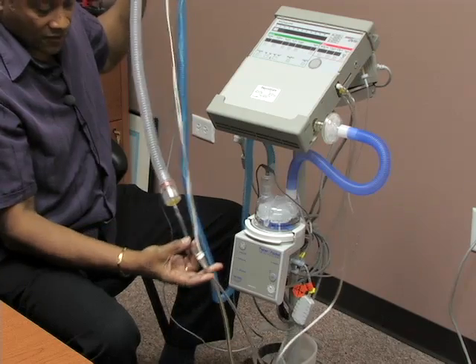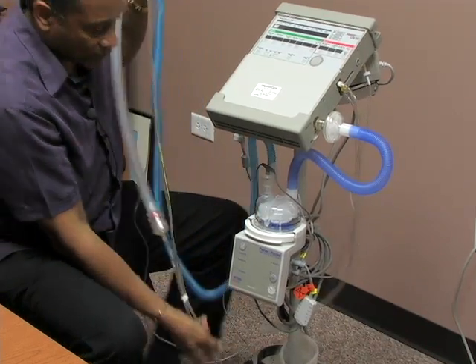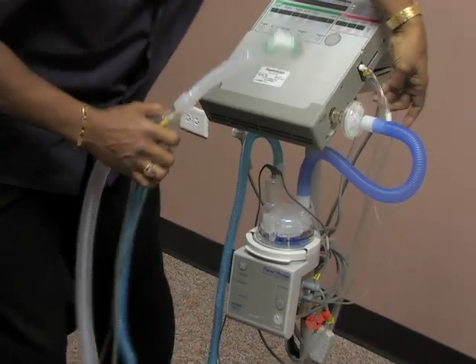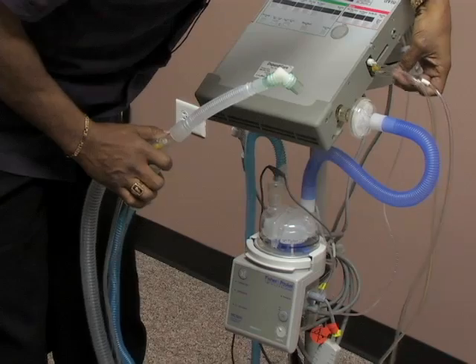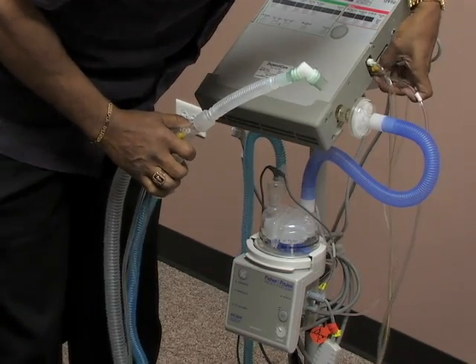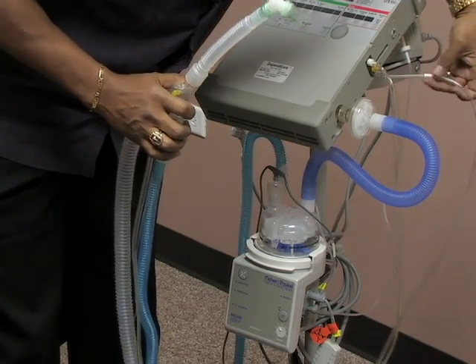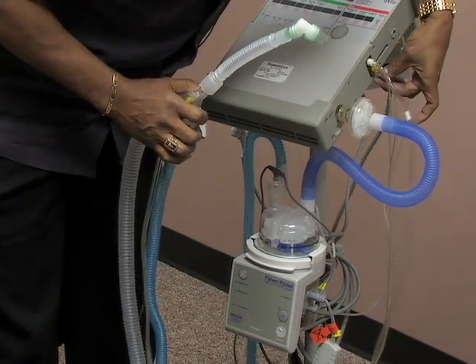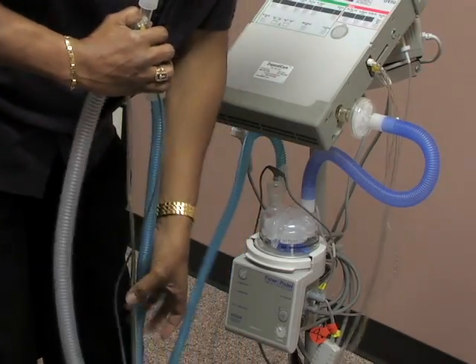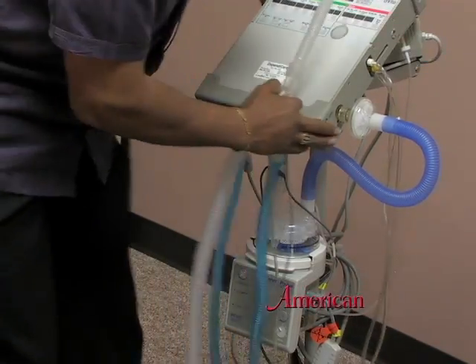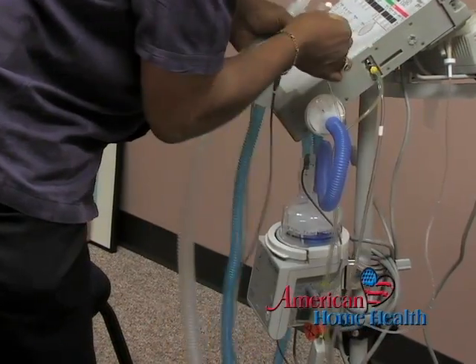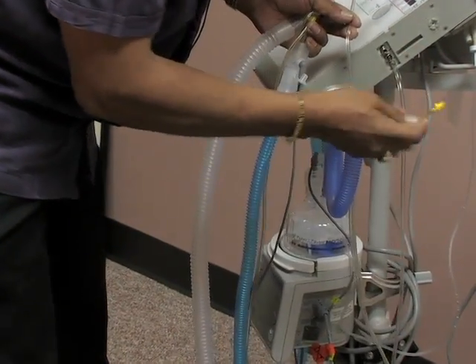The tube comes out of here from the PEEP valve and comes around to your transducer. These sense lines come into the transducer. All of your exhalation values, like your PEEP, are read here. The other sense lines also come here, and they're read here at these transducer ports.